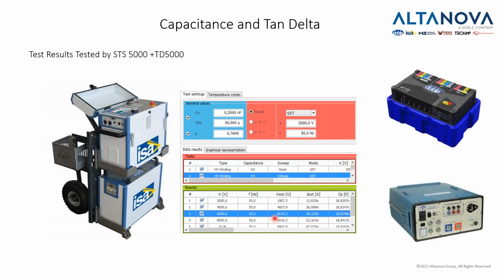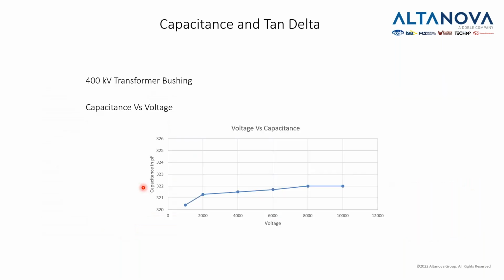This would be some results. So in this case, we generated different voltages, and we obtained the same capacitances, which is important. You can use M7 or M4 or STS plus TD or TDX to do this type of test. And of course, you will do this test at nominal frequency, and the voltage doesn't need to be more than 12 kilovolts, even though 10 is often more than enough.